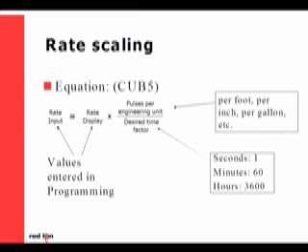Our equation for determining the rate input is: rate display times pulses per engineering unit, over desired time factor. When we are programming our rate meter, the rate input value and the rate display value are entered. The rate display, or desired reading, should be set at the fastest rated speed for your application. Our time factor is used to determine what scale we are measuring at — it can be in seconds, minutes, hours, or so on. If our time factor were in seconds, you would use a 1; per minute, you would use a 60; and per hour, you would use 3600.